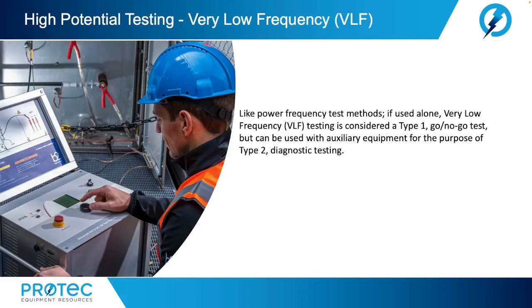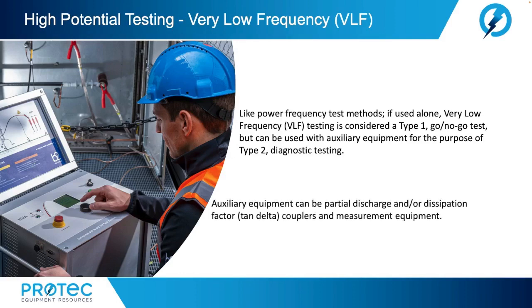Now, like power frequency test methods, if used alone, very low frequency or VLF testing is considered a type 1 go, no-go test, but it can also be used with auxiliary equipment for the purposes of type 2 diagnostic testing. Auxiliary equipment can be partial discharge detecting equipment and or dissipation or tan delta couplers and measurement equipment.